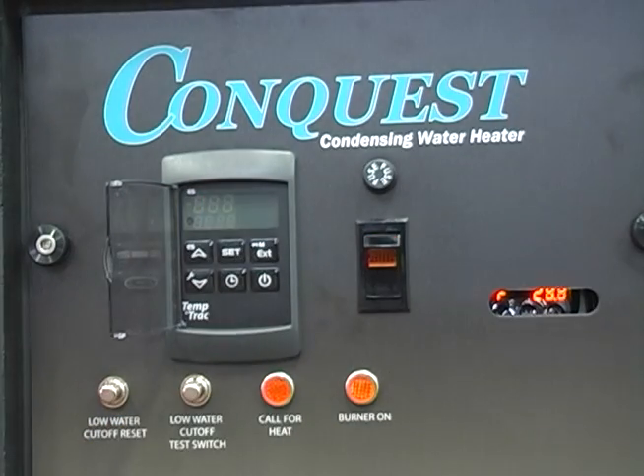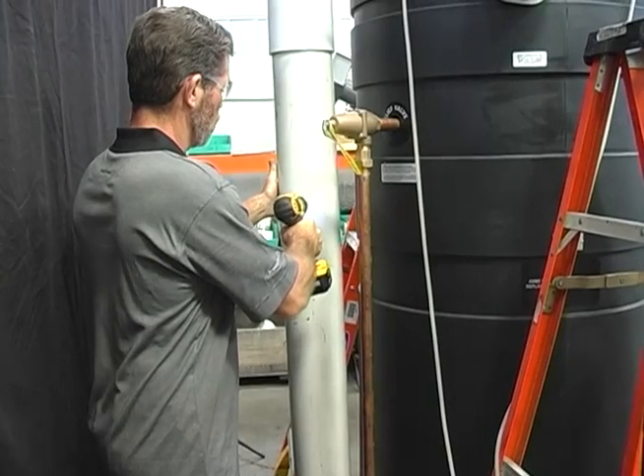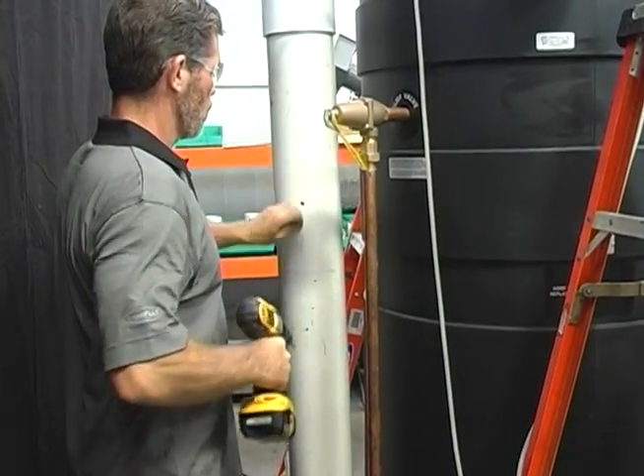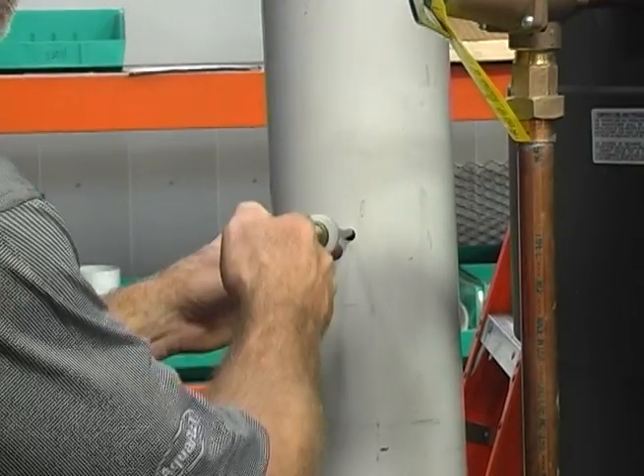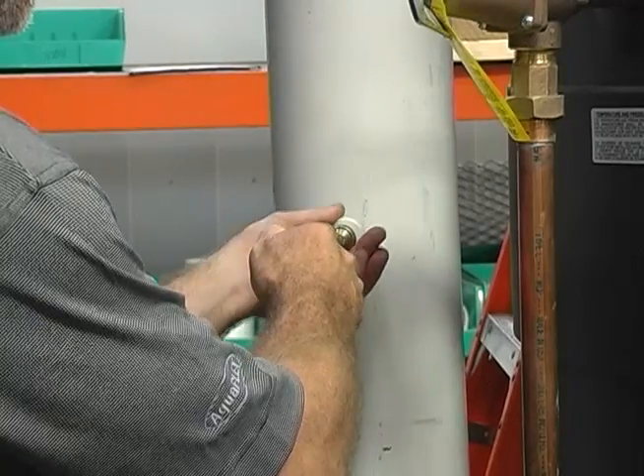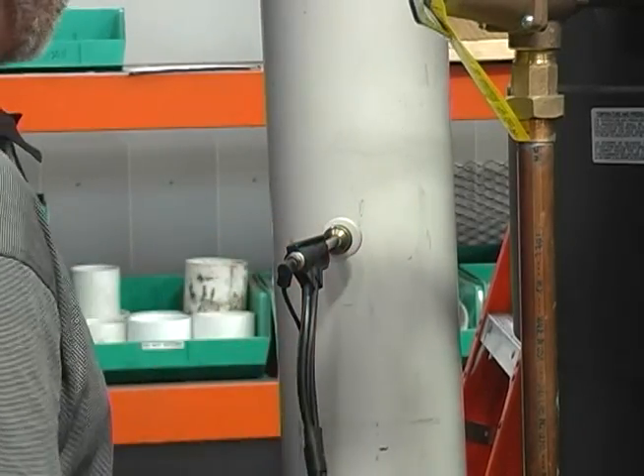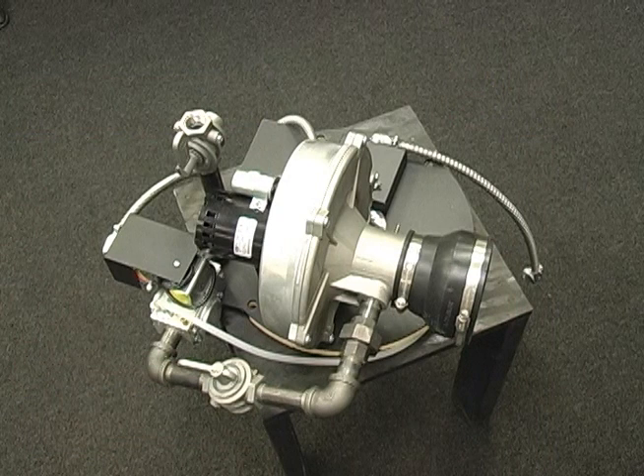To adjust combustion, begin by moving the rocker switch to the off position. Drill a small hole in the vent approximately 2 feet from the appliance vent connection. Insert the combustion analyzer probe into the hole. The Conquest water heater is manufactured with 2 types of burner systems.